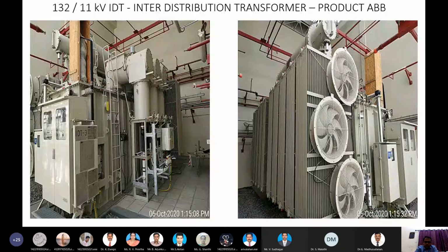This is the transformer. Again, it is an ABB product. We also had Alstom, GE, and Hitachi transformers, which we used in our previous substations in our previous countries. This ABB transformer is, if I'm not wrong, from Germany. We have specific engineers from the German manufacturer who come to the country and install the equipment as per the design. Once the installation is done, there is oil filtration, then testing from level 1 to 3, and then it is commissioned for the rundown.